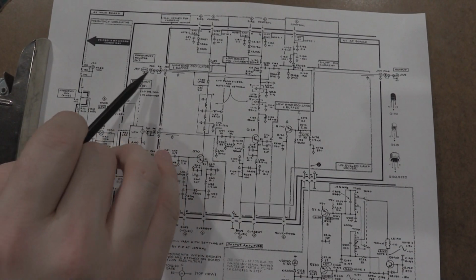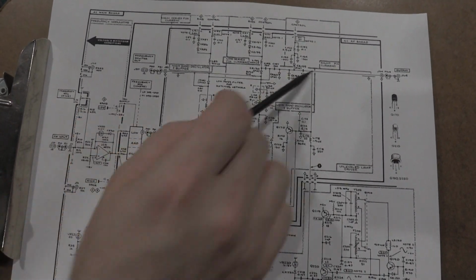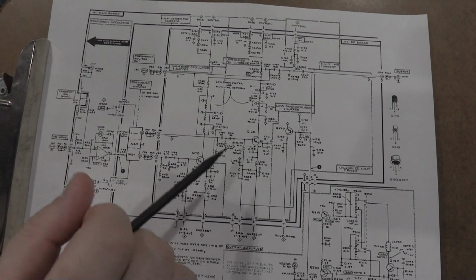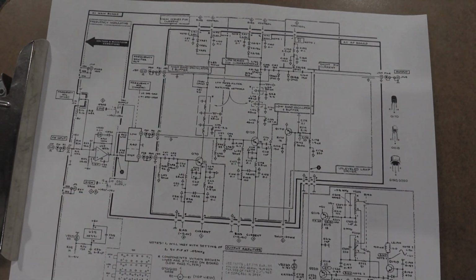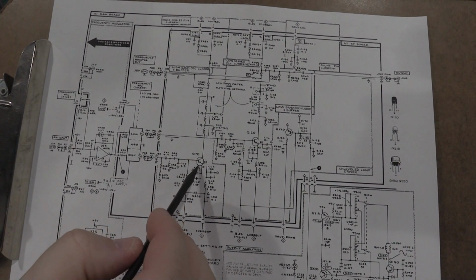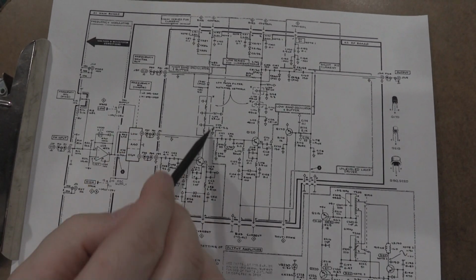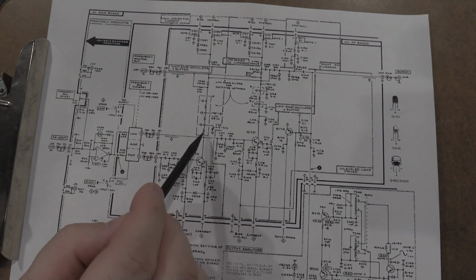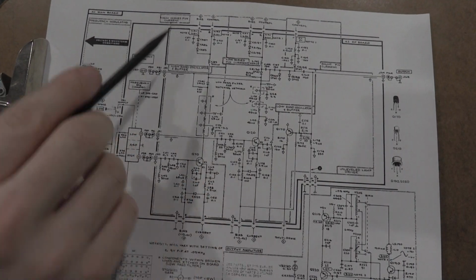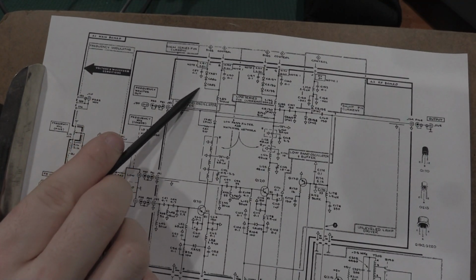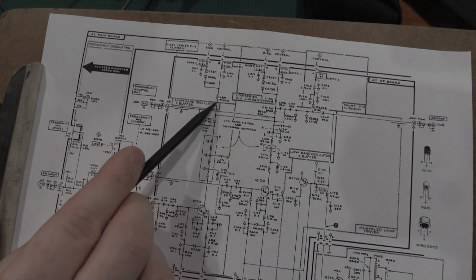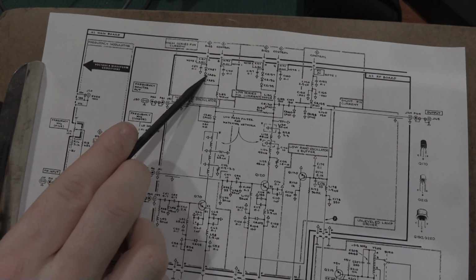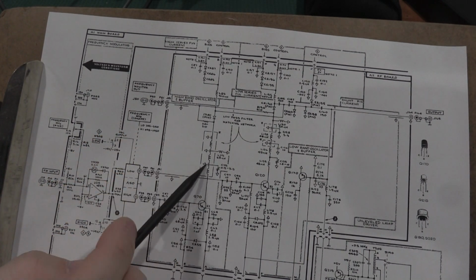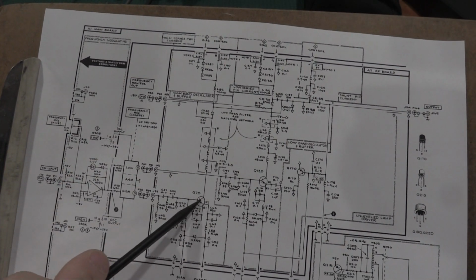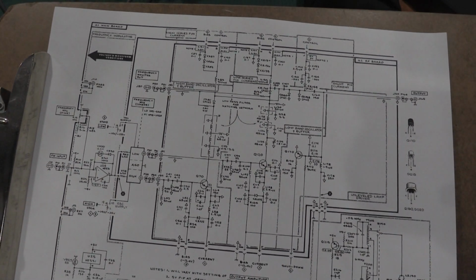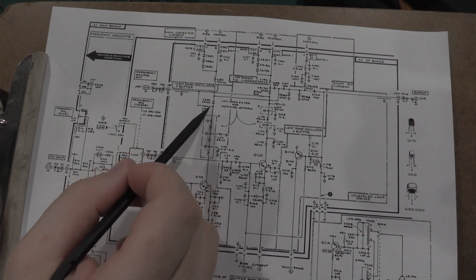I'm going to set up the DSA again, and we'll do some testing at the frequency output and see what we get. Should be telling as to if we're getting enough drive. If we're not getting enough drive out of Q70, I'm going to test this transistor, but I'm also going to look at voltage supplies, because if one of these diodes is opened or high resistance, and I'm not getting enough voltage through to the collector, it won't be able to swing enough to generate the signal that I need.